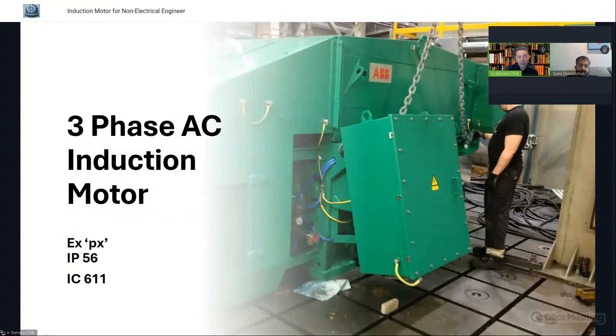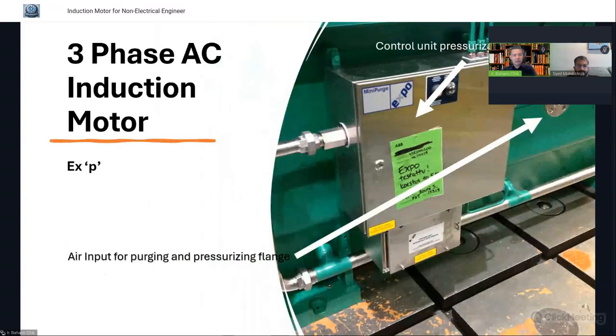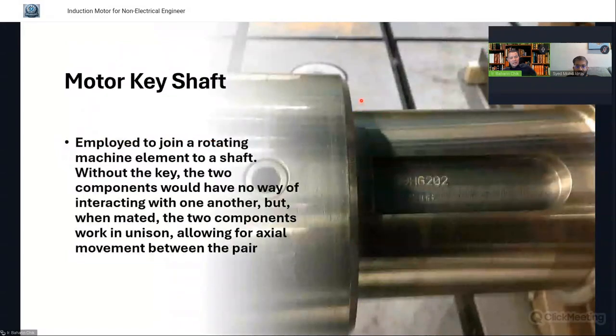This is another project that I made, Ex px, with IP56 and IC611. Now, since we have Ex p, that means this motor is pressurized. We have a control unit here for the system. And then also we have the purging flange for the connection to the instrument air. The other important part is actually the motor key, where this is connected to the pump and motor shaft, so that they can rotate together.